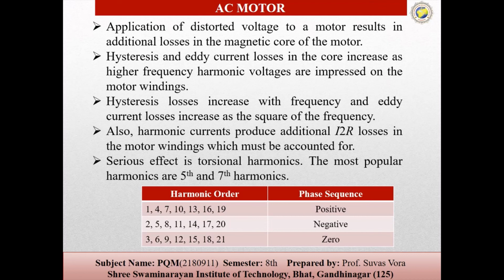So here, a 10 degree Celsius increase in the temperature reduces the life of the induction motor by 50%, and the squirrel cage motor operates better under these conditions than the wound motors. So another serious effect is from the 5th and 7th harmonics. So for the 7th harmonic, the magnetic field rotates the same as that of the fundamental field, and the interaction between the magnetic field and the fundamental field generates oscillations in the shaft of the motors.